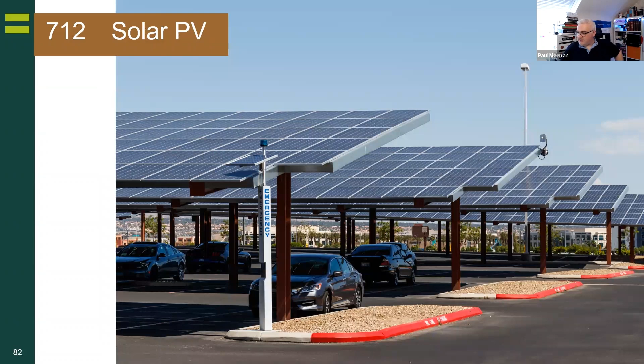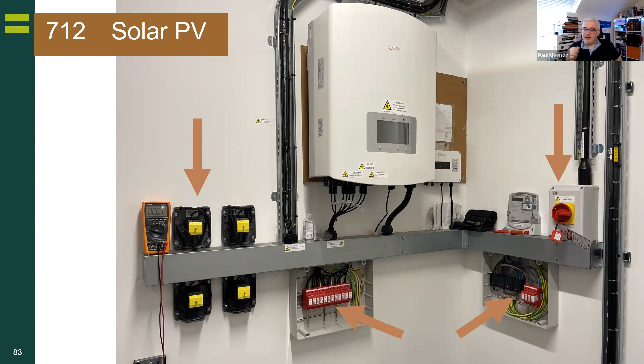There are requirements now within 712 to have correct isolation and surge protection considerations. This has all come from the BSEN standards. Now, your inverter could do this, but from my safe system work perspective, I want my electricians to be able to isolate the DC safely, isolate the AC safely, and then remove the product in between.